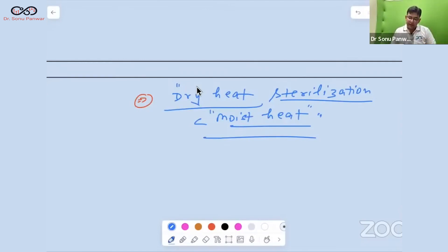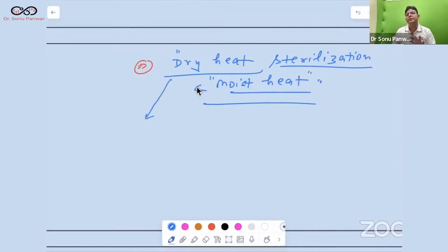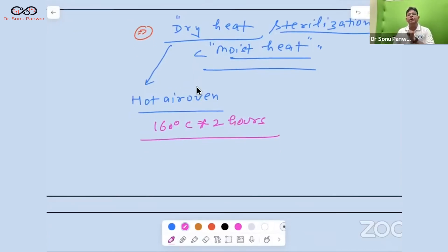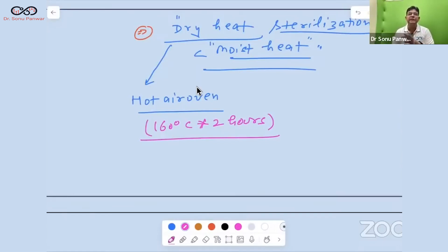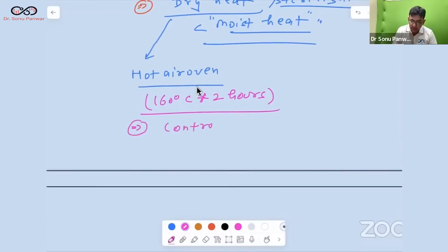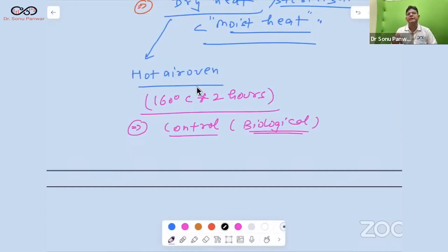In dry heat sterilization, the most important instrument is the hot air oven. The temperature should be 160 degrees centigrade for two hours. Glassware, certain surgical instruments, grease, paraffin, and dusting powder are all sterilized by the hot air oven. An important exam question: what is the biological control used for the hot air oven?